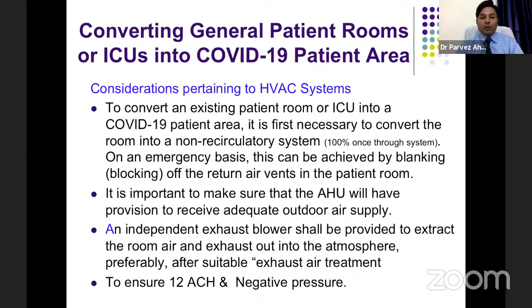It is important to make sure that the air handling unit has provision to receive adequate outdoor air supply. We also have to ensure a safe location of the AHU. It should be away from the parking area or any contaminated zone. An independent exhaust blower shall be provided to extract the room air and exhaust it into the atmosphere, preferably after suitable exhaust air treatment. So ICU to ensure minimum 12 air changes per hour with negative pressure of 2.5 pascals.